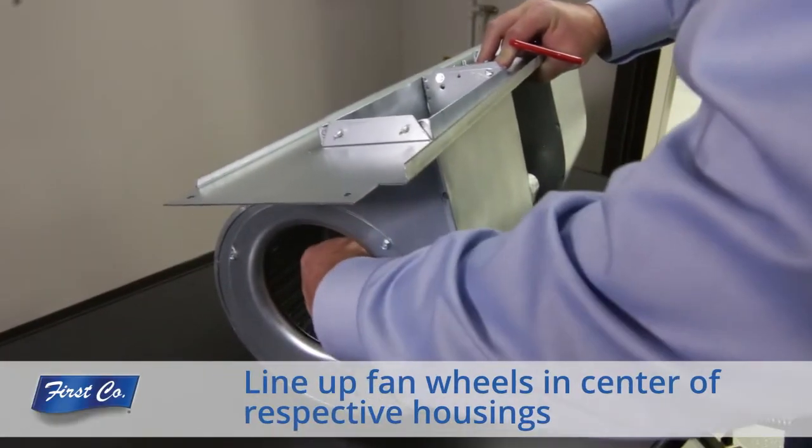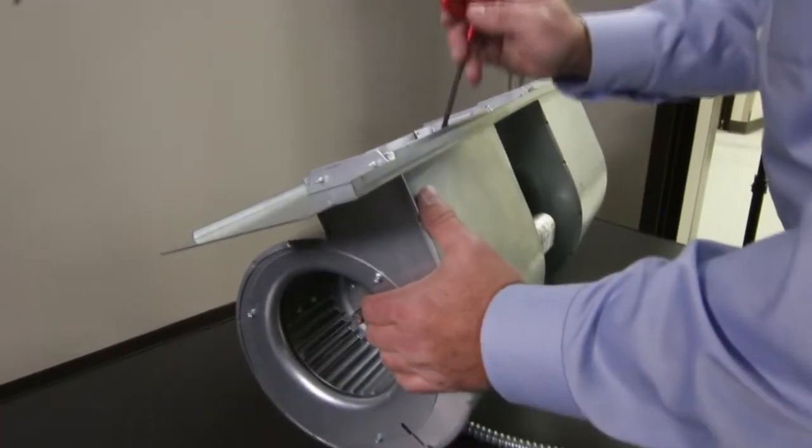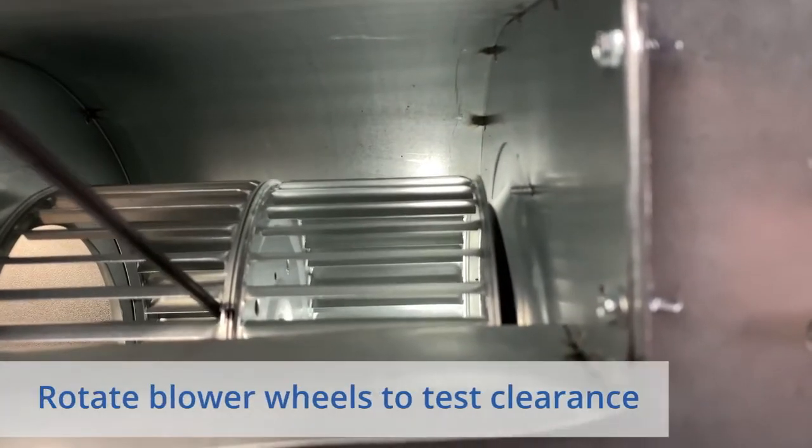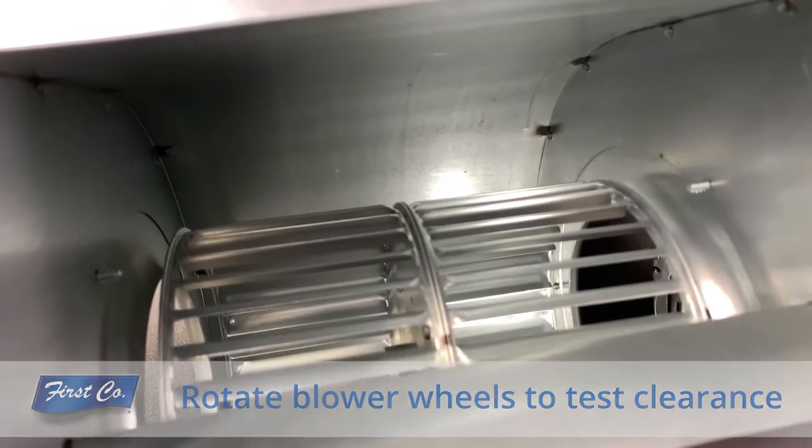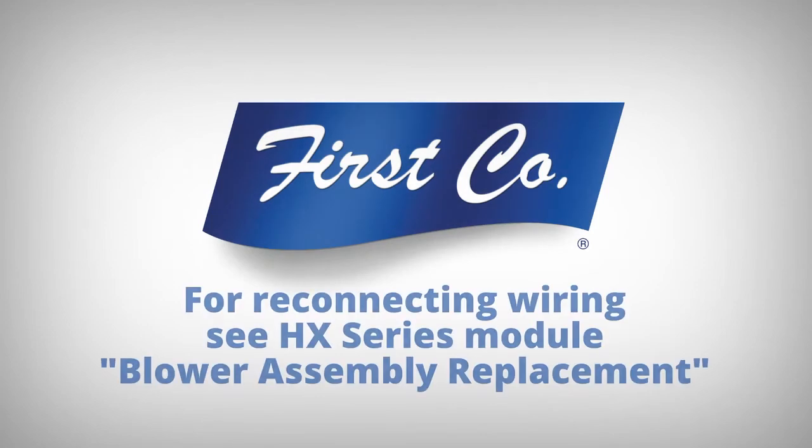Line up the two fan wheels in the center of the respective housing and using the T-handle Allen wrench, tighten down on the set screws. Rotate the blower wheels to make sure they are rotating freely and not rubbing on the housing. Refer to the blower housing removal and replacement video for more details on reconnecting the wiring.